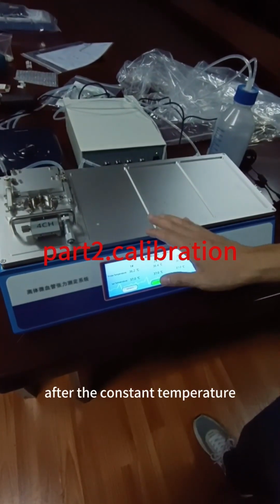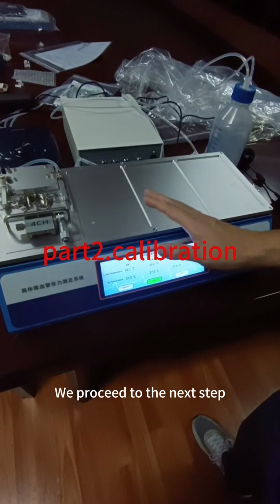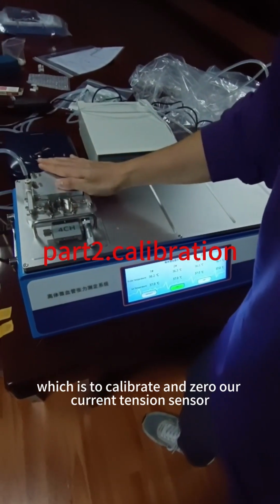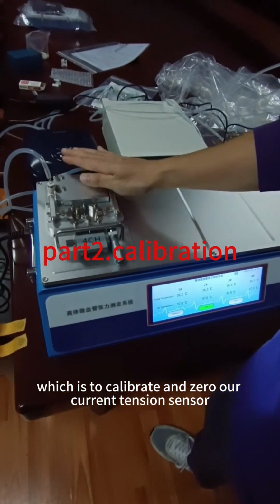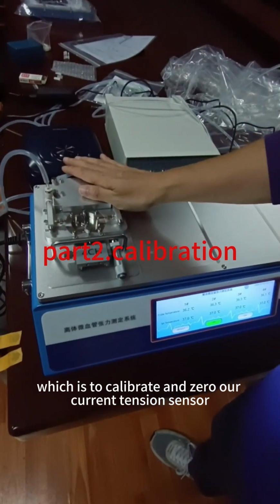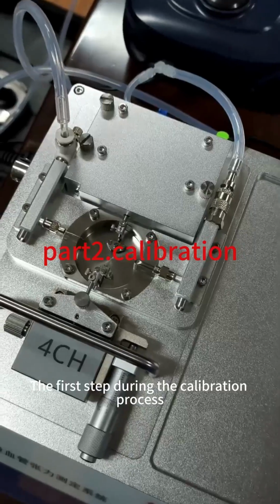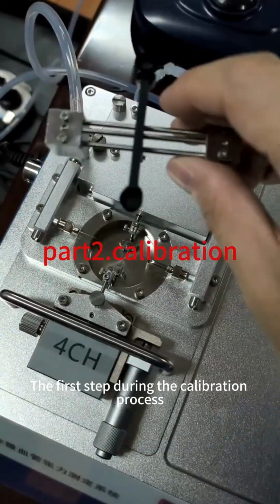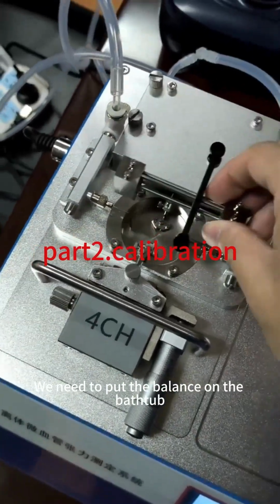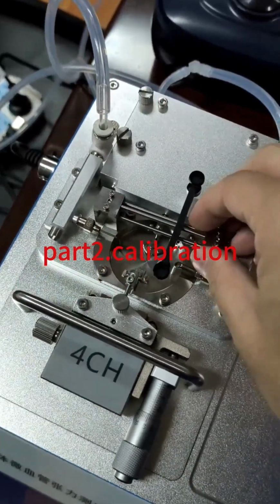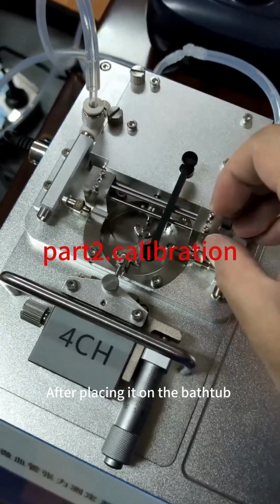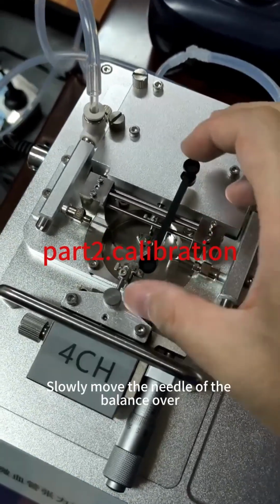After the constant temperature, we proceed to the next step, which is to calibrate and zero our current tension sensor. The first step, during the calibration process, we need to put the balance on the bathtub. After placing it on the bathtub, slowly move the needle of the balance over.